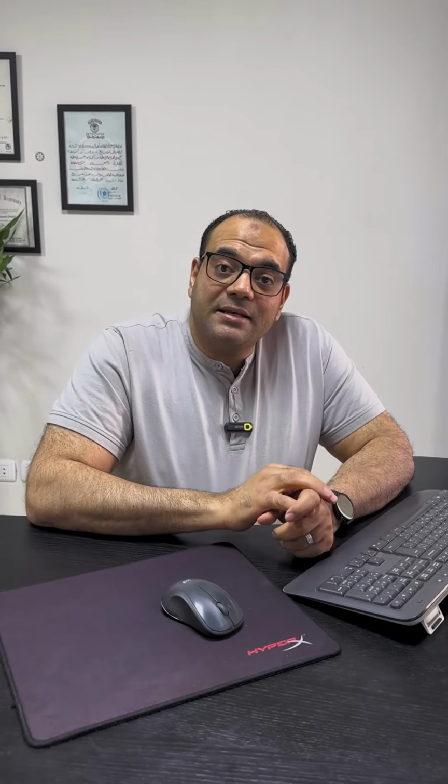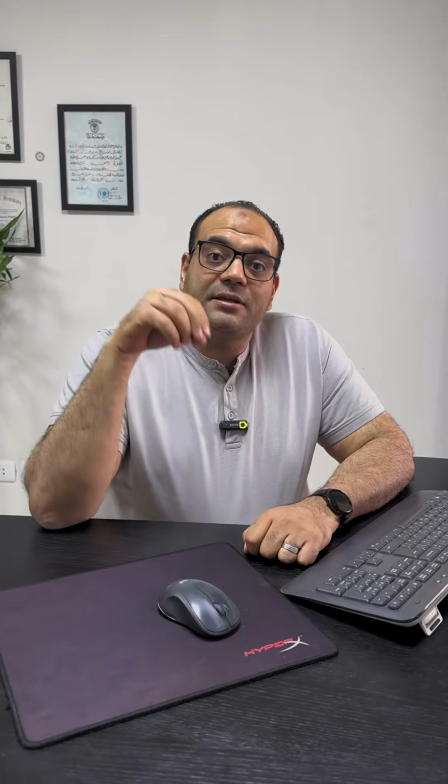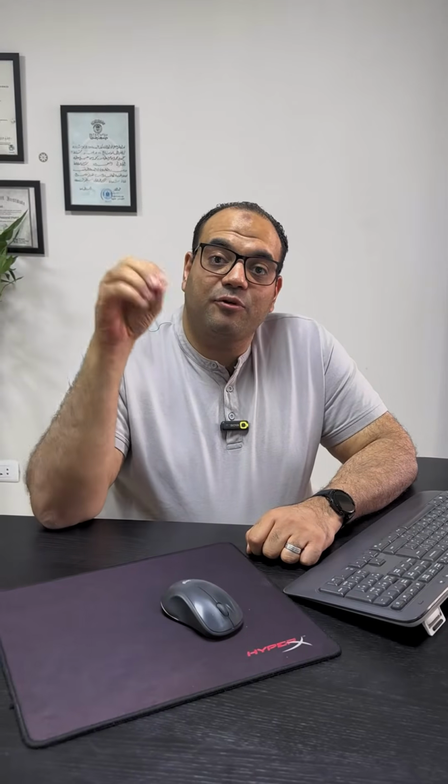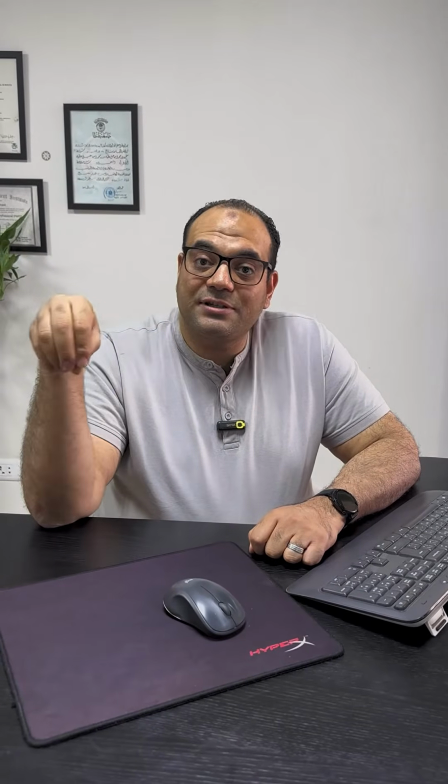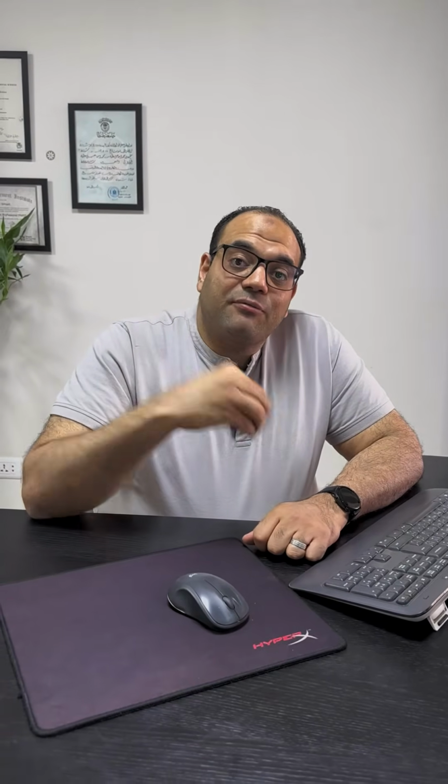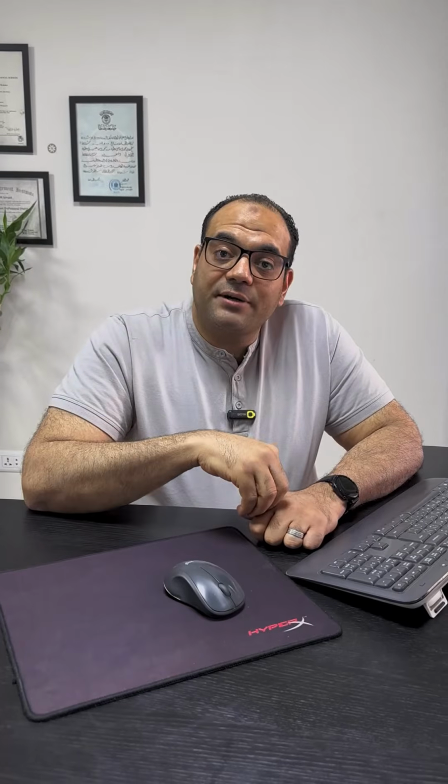The other test is to be sure that the air is coming from the outlets. After we are sure that it is working, the air is flowing and the air is coming from the proper outlets, with no leakages, now we'll start the balancing. Balancing means the volume of air and the temperature of air as per the required specs.